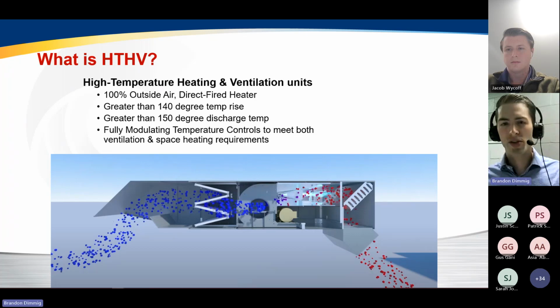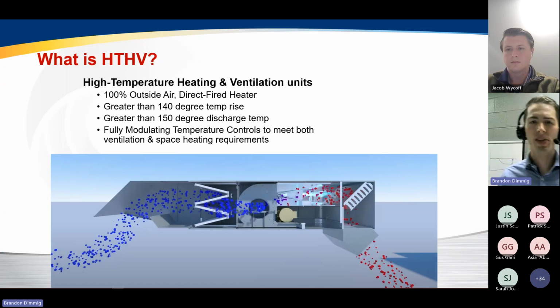From a basic definition standpoint, HTHV stands for high temperature heating and ventilating. And there's a couple of criteria that you have to meet in order to be classified by this. It's actually a definition that the Department of Energy has created. It requires 100% outside air. It's a direct fired unit. You must have greater than a 140-degree temp rise, and you must be able to discharge air at greater than 150 degrees. You also must be able to meet ventilation and heating requirements simultaneously with some sort of modulating control system.